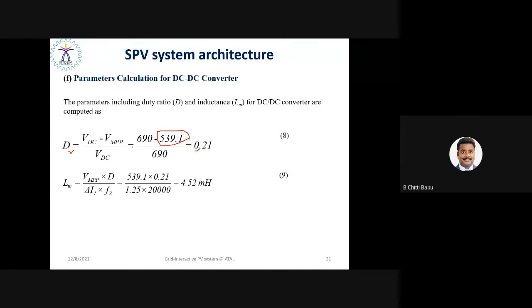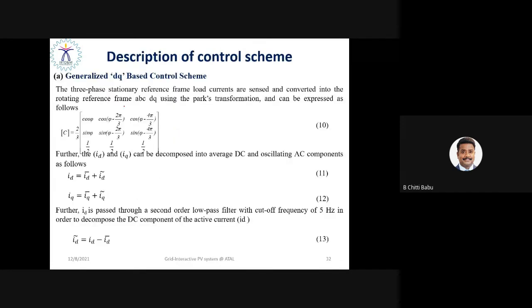We are boosting into 690 in order to transfer 13.5 kilowatts of PV power to the DC link capacitor. We assume the ripple current would be 25% of the rated current. As the current is basically a PV output current that varies instantaneously, we can take the worst case of 25% of the rated current. Along with the switching frequency of 20 kilohertz of the boost converter switch, we designed the inductor value at about 4.52 millihenry.